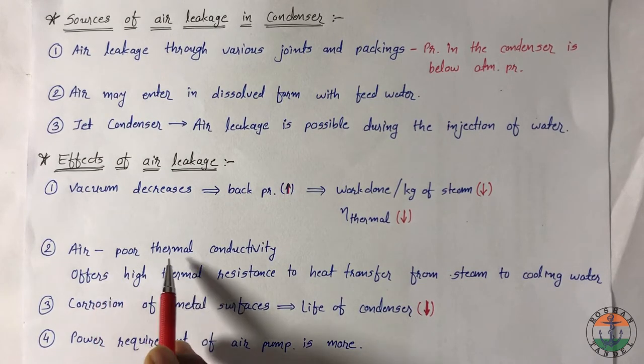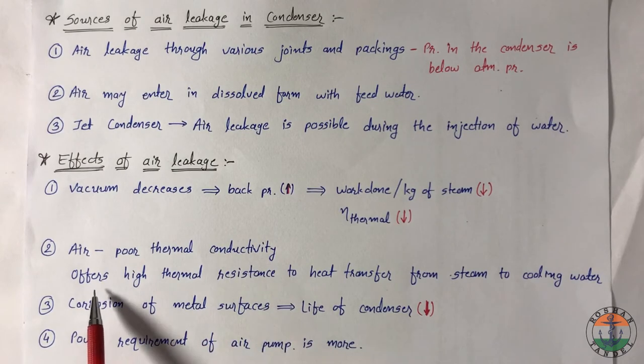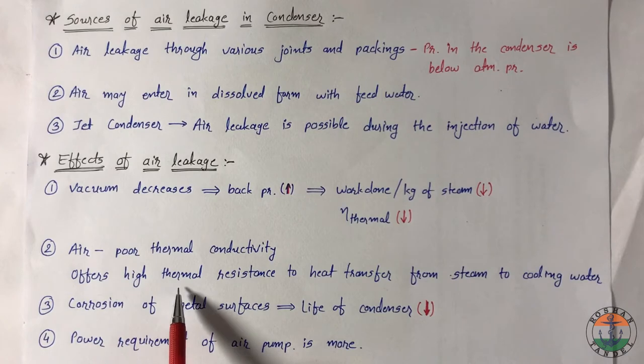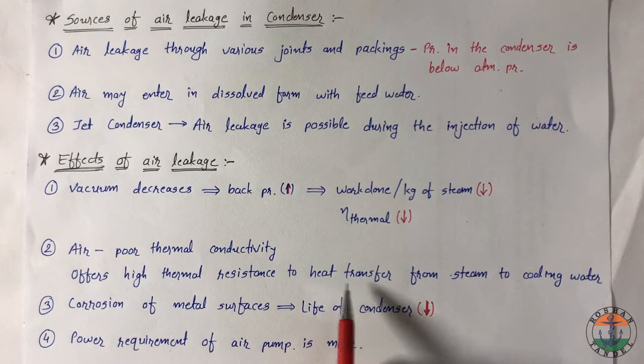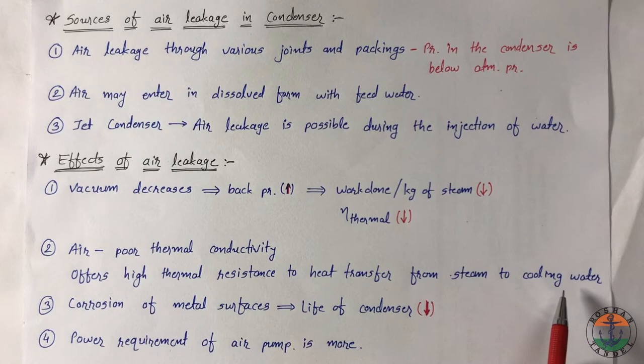Air has a poor thermal conductivity. Presence of air offers high thermal resistance, so heat transfer rate from steam to cooling water decreases. Air in the condenser causes corrosion of metal surfaces which reduces the life of condenser. To remove the air, air ejector pump is used. If air leakage is more, then power required to drive that pump is more.